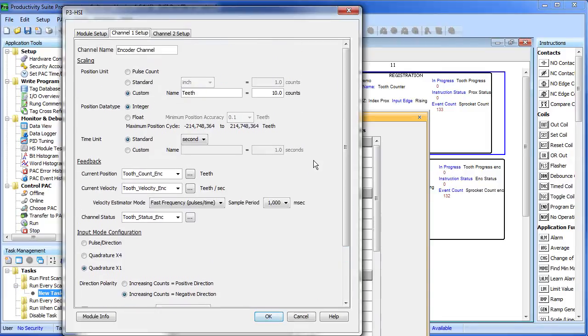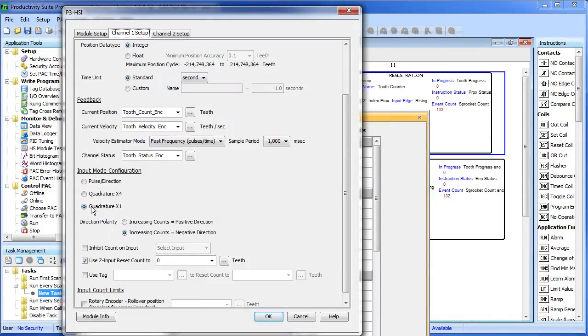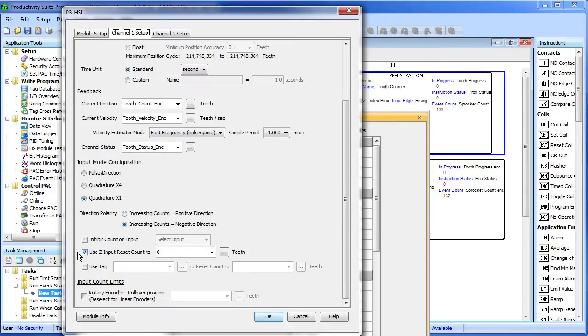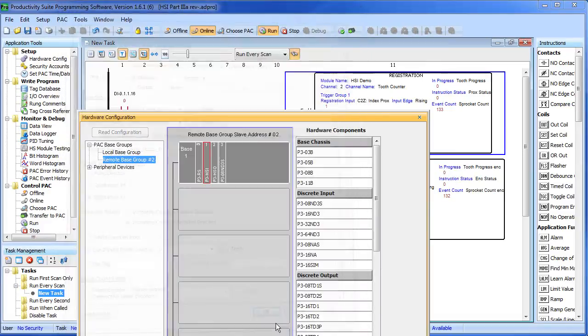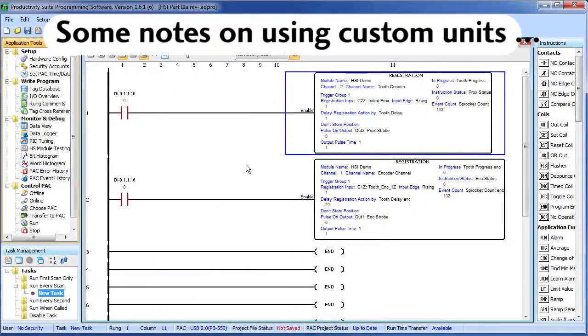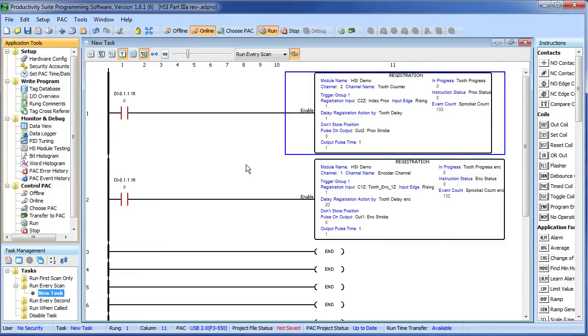So that's it. It's the exact same settings we had in the previous demo, except we modified our custom units to be 10 counts per tooth to account for the encoder. Gave the encoder tags a slightly different name, selected a quadrature encoder times 1, and now we're using the Z input to reset the tooth count. Select OK. We're done configuring the HSI module. So understand the beauty of using those custom units. Since all of our ladder code was using teeth, all we had to do for the encoder was modify that custom unit to be driven by 10 pulses.